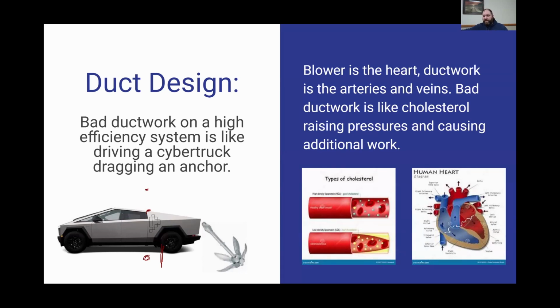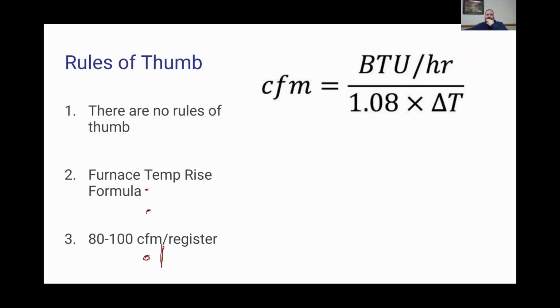We analyze the ductwork on every HVAC system we replace, because no matter how great the equipment is, if it is poorly installed, and the biggest implication of it being poorly installed is the ductwork, it will fail prematurely. You will not get the life out of it. It will not work. So a lot of guys will say there's some rules of thumb when it comes to duct designs. I would say point number one, there are no rules of thumb. If you're operating fully based on rules of thumb, you're going to make mistakes, especially when we get to high efficiency equipment.